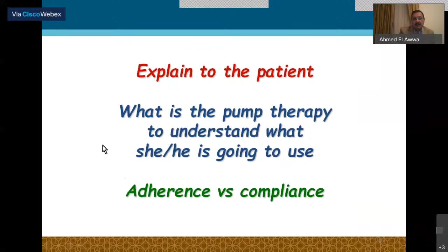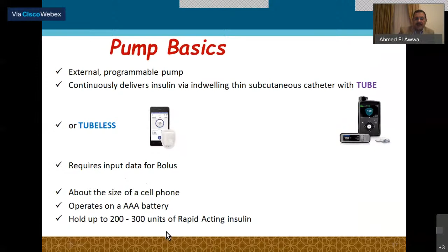So just to know about the insulin pump, it's an external programmable device that continuously delivers insulin via an indwelling thin subcutaneous catheter, by a tube or without a tube. Now some pumps are tubeless, and most of the pumps on the market are with a tube. It still requires input data for the bolus, so you need to enter how much carbohydrate the patient is consuming. For the calculation, the pump has settings for the insulin carbohydrate ratio and the insulin sensitivity factor, or the correction factor. So the patient still needs to give data to the pump. It's operated by an AAA battery, most of them, and holds from 200 to 300 units of rapid-acting insulin.